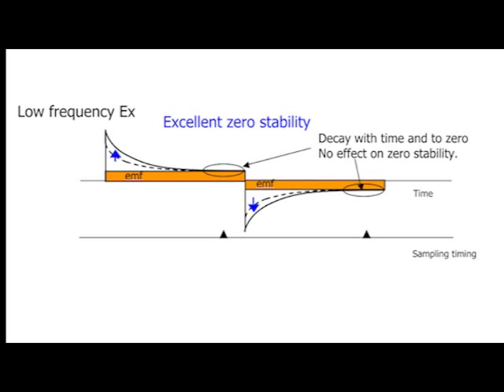In the low frequency excitation method, the coil excitation frequency is low, allowing the induced noise to decay with time and decrease to zero where it is sampled. By sampling the portion of the signal where induced noise doesn't exist, the induced noise can be canceled even if the waveform changes. Thus, low frequency excitation can maintain excellent zero stability.